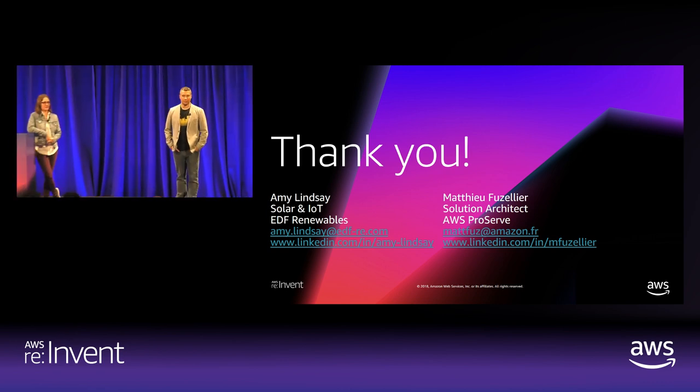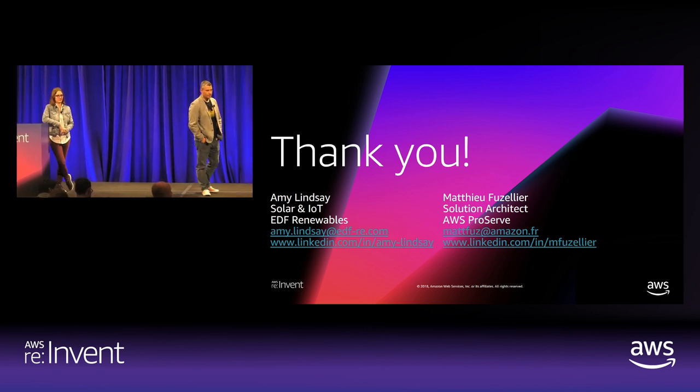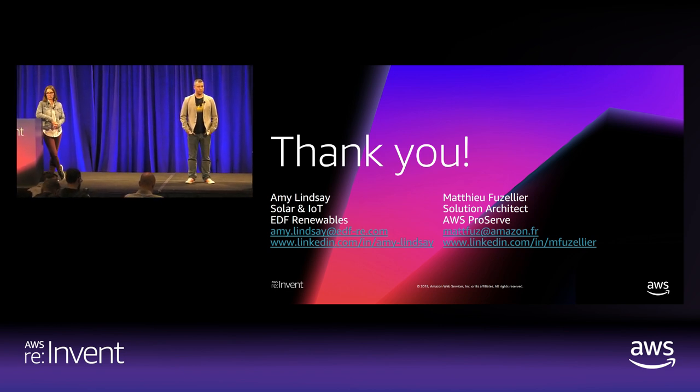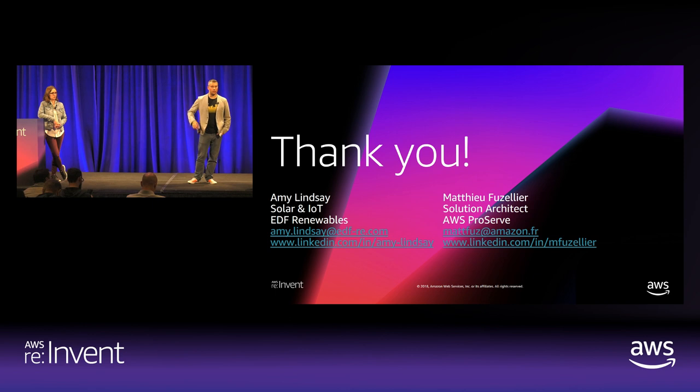All right, we have a couple more minutes if any of you guys have any more questions. This POC, how are you guys converting DNP to MQTT? You had to write your own adapter? Yes, so that's going to be the code that we deploy within Greengrass that's going to act as a protocol adapter. For our proof of concept, we focused on Modbus. This code that we developed is able to pull Modbus registers, get the data, do the data cleanup and aggregation that I showed, and then convert that into a piece of JSON that is then sent over MQTT by the Greengrass core.